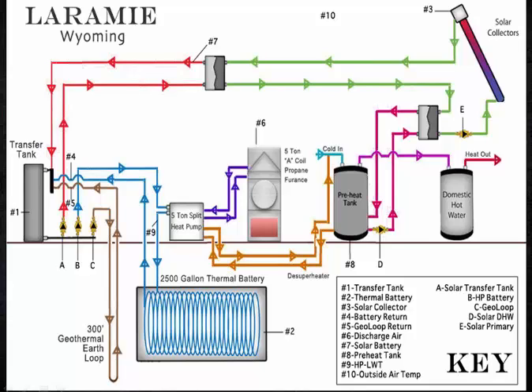if you were just pumping the water from the tank in the ground through the heat pump and so on, you would not get the latent capacity of it because you'd freeze up in the heat pump and then it'd be over. The moment you got to 38-degree water, it'd start freezing in the heat pump because it's going to be discharging at around freezing at that point, and it'd be over. Whereas if you freeze protect that thermal battery loop, you can pull it all the way down to 25-degree entering water before you're risking locking the thing out on low pressure.